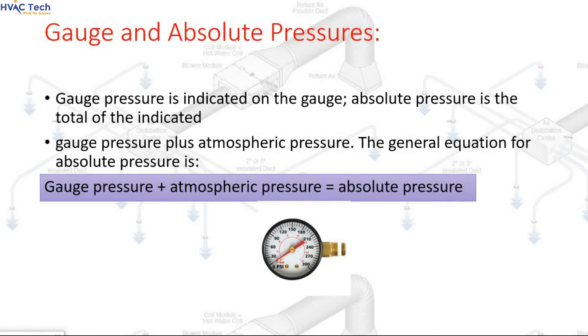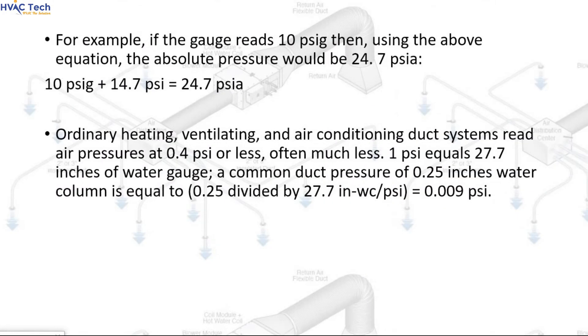Gauge and Absolute Pressures: Gauge Pressure is indicated on the gauge. Absolute Pressure is the total of the indicated Gauge Pressure plus Atmospheric Pressure. The general equation is: Gauge Pressure + Atmospheric Pressure = Absolute Pressure. For example, if the gauge reads 10 psig, then using the above equation, the absolute pressure would be 24.7 psi.